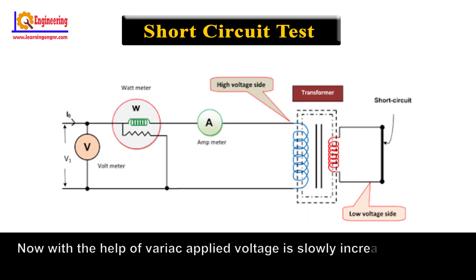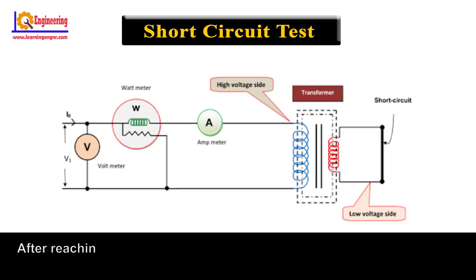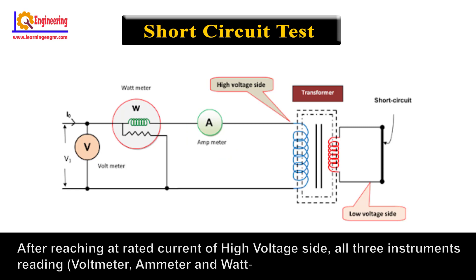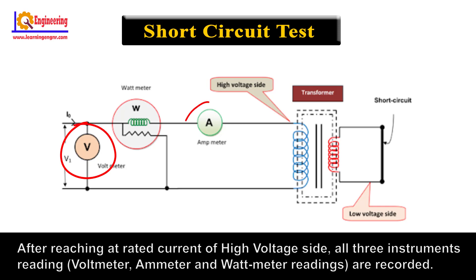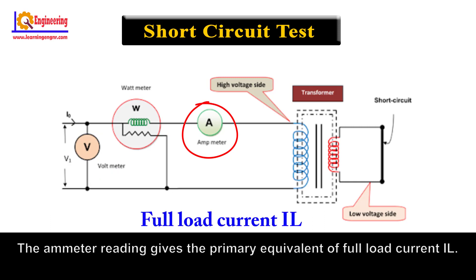With the help of the variac, the applied voltage is slowly increased until the ammeter gives a reading equal to the rated current of the high voltage side. After reaching the rated current of the high voltage side, all three instrument readings — voltmeter, ammeter, and wattmeter — are recorded. The ammeter reading gives the primary equivalent of the full load current IL.